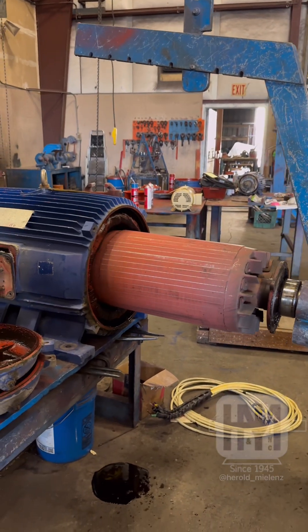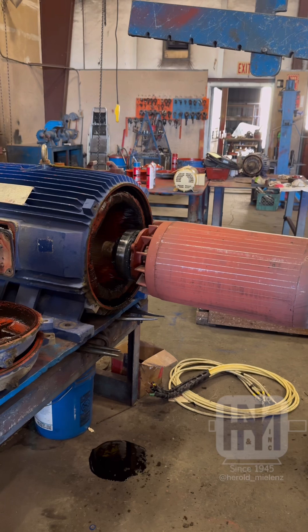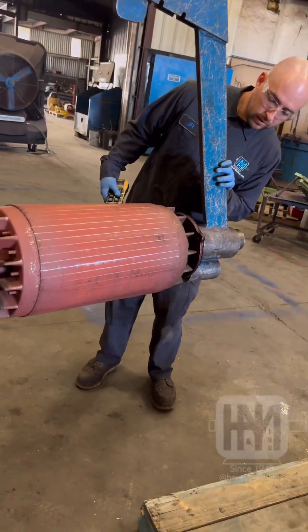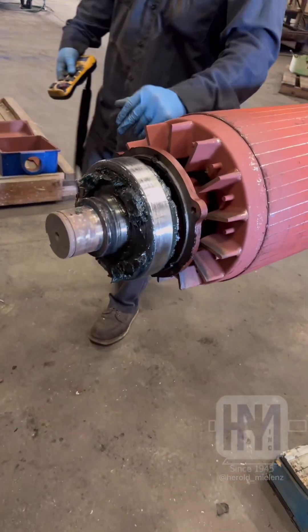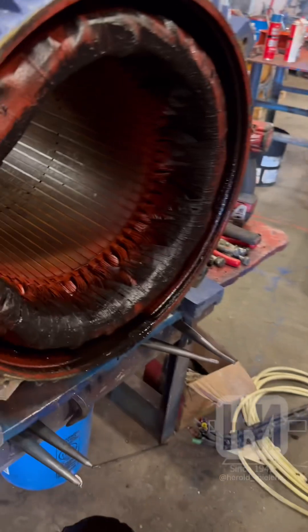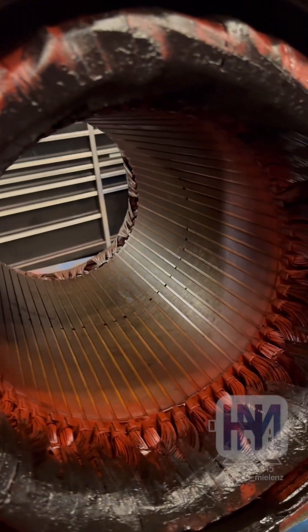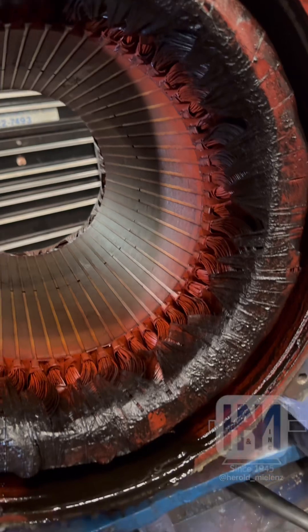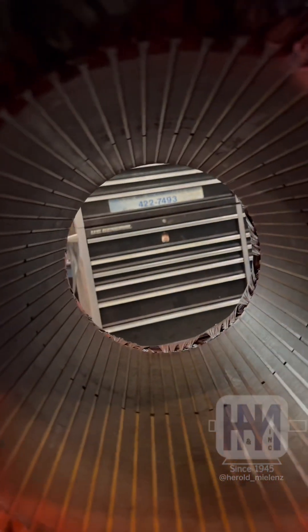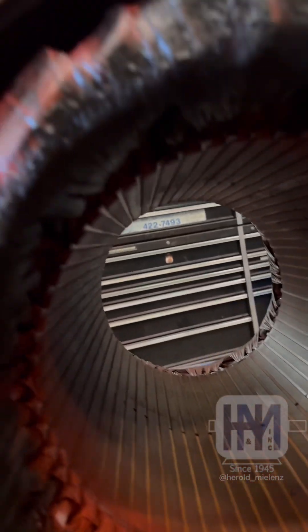We have our rotor toter here. Let's get an internal look at this winding — a little dirty, but overall nothing a little cleaning and VPI won't fix. We need to change the bearings. General recondition piece though.